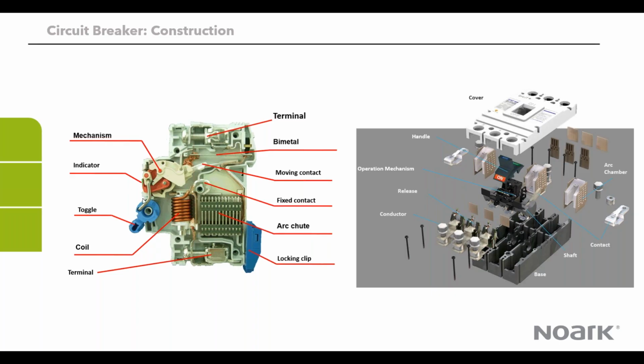You basically have the indicator here, which tells you the status of the breaker. The toggle is what you use in controlling, so you can either close or open the contact using the toggle. The toggle also has a middle position, which is the test, which is a trip position. Basically, when there is a trip, it goes into the middle position. And then you have the coil, which is responsible for short circuit sensing, to be able to sense the short circuit and then cause a trip to happen.